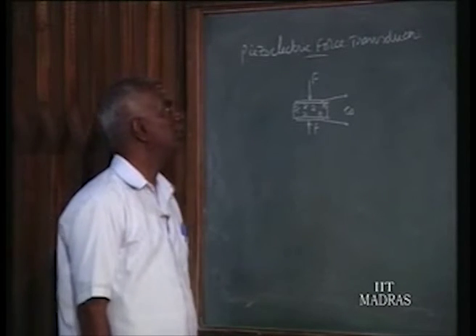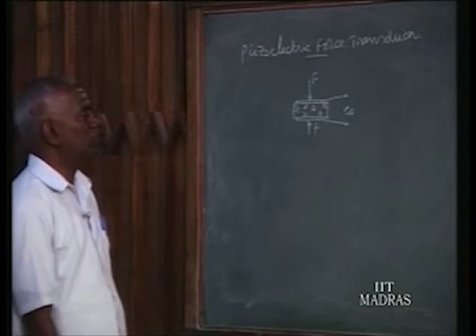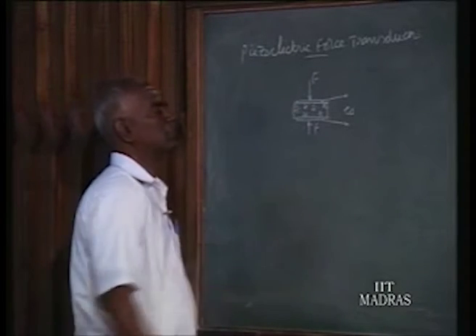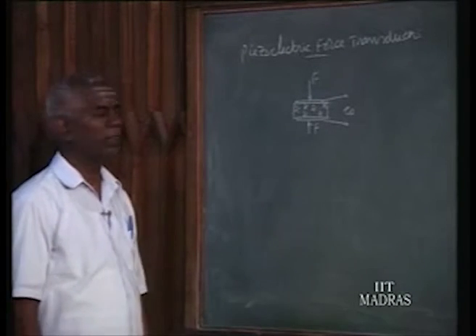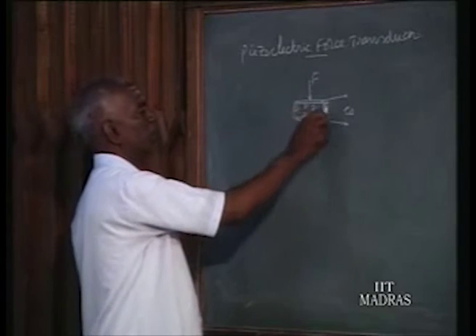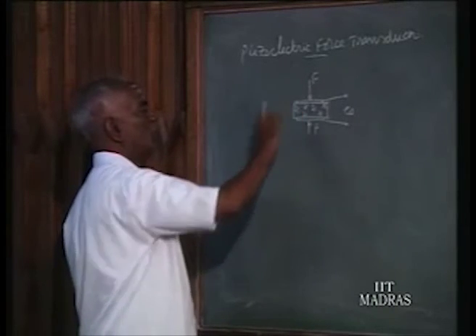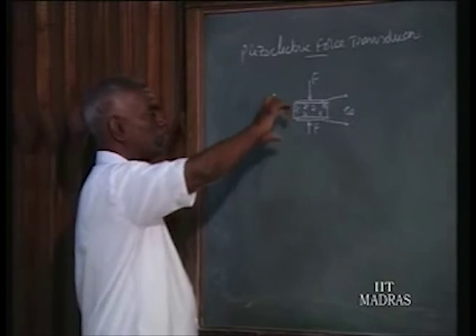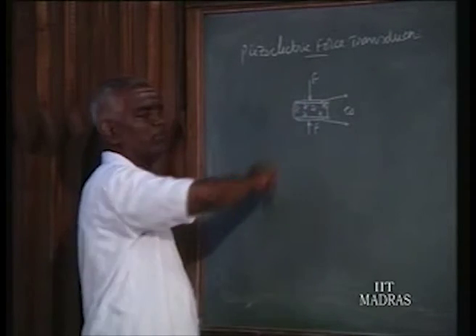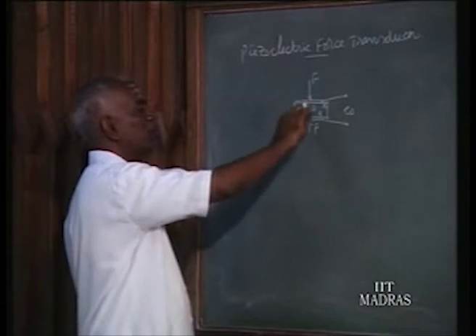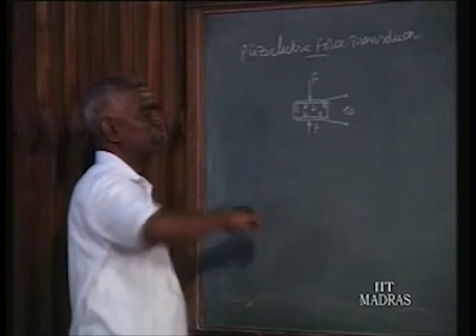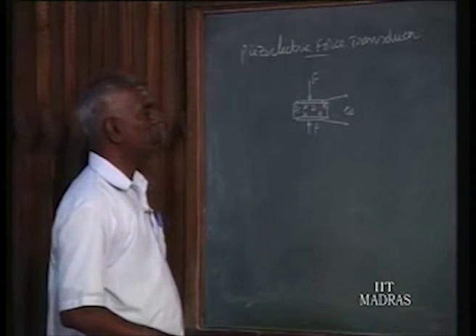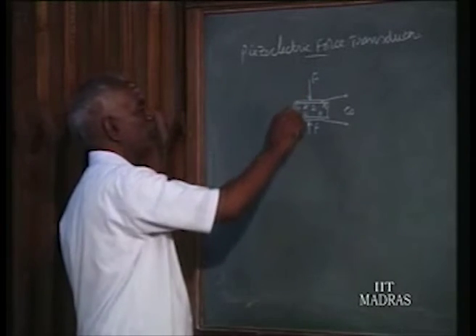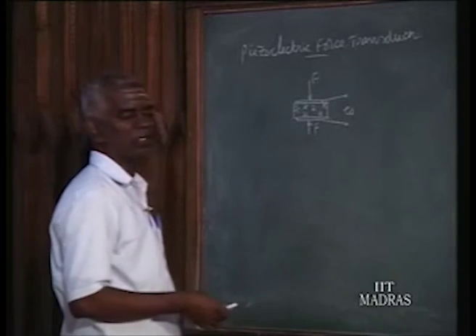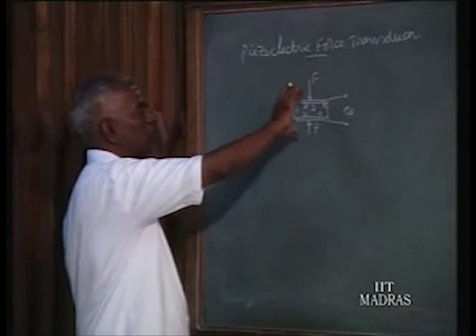Next we see the piezoelectric force transducer. We know the piezoelectric crystals respond to dynamic loads. We can apply the load to this crystal and it can give either a displacement signal or a force signal. A displacement signal alone we cannot get without a force, because the crystal will not deform; it has a very high spring constant. So now we use it for measuring force. Apply the force, then it deforms.